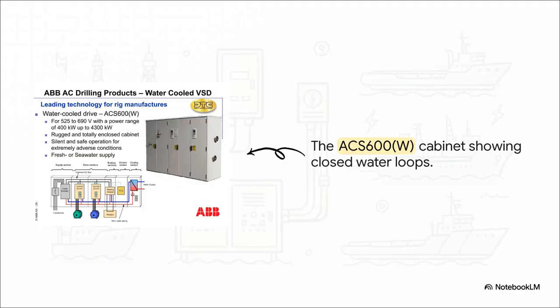That's a recipe for disaster. By specifying a water-cooled cabinet, the enclosure can be completely sealed tight, stopping salt air ingress dead in its tracks. Inside that sealed cabinet, a closed freshwater loop actually cools the sensitive electronics. That warm fresh water then rejects its heat through a plate heat exchanger to seawater drawn from the hull. So the salt water takes the heat away, but it never touches the internal gear.